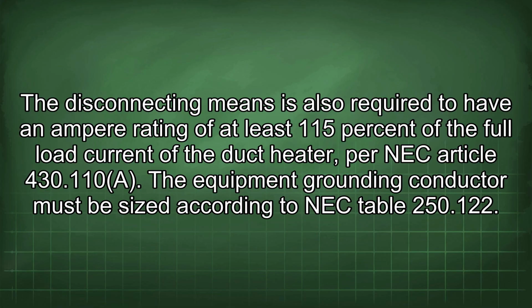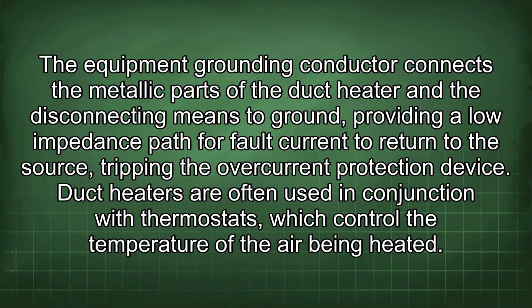430.110(A). The equipment grounding conductor must be sized according to NEC Table 250.122. The equipment grounding conductor connects the metallic parts of the duct heater and the disconnecting means to ground, providing a low impedance path for fault current to return to the source, tripping the overcurrent protection device.